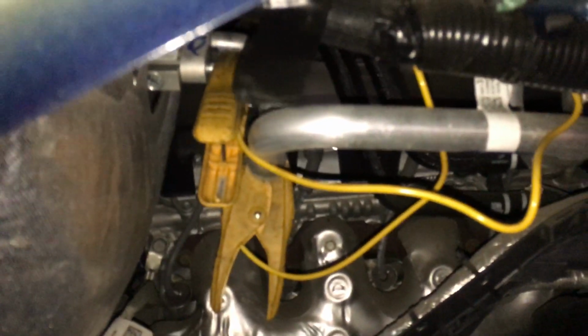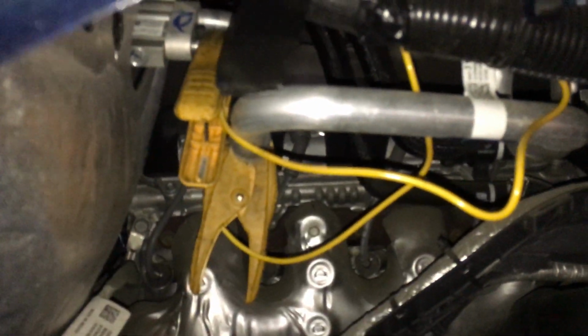Okay. So then the next temperature we're doing, this has an internal heat exchanger on the liquid line. And this is the thing I've been mentioning to a lot of you guys who are used to grabbing the pipes and determining whether a system is full or not. Old school method that you can't do anymore with these kind of units. Okay, so you notice this is extra large here. This pipe is 7/8, 1 inch, 24 millimeters wide right here. So when you get right here, this is the same pipe.